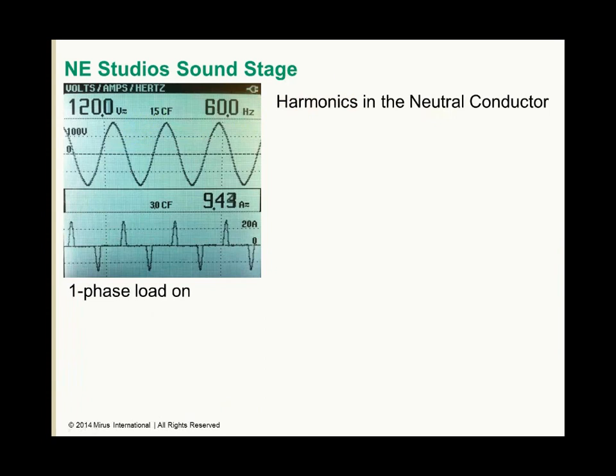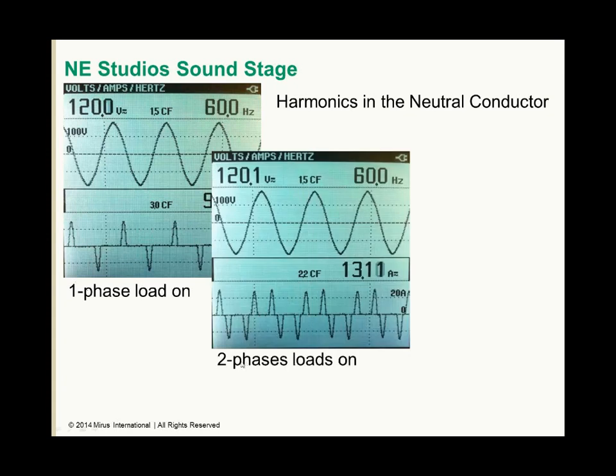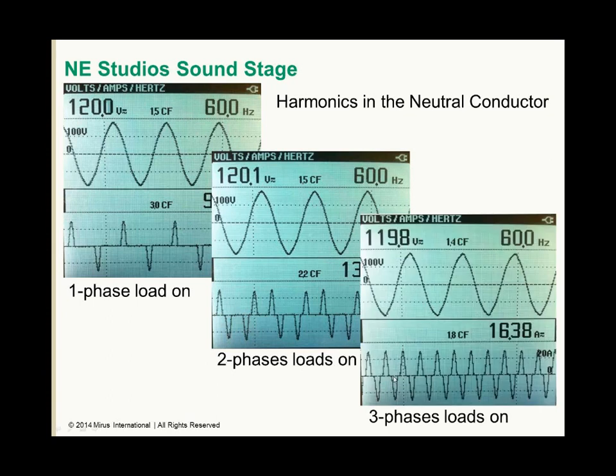Switching the loads while measuring the waveforms shows how the pulse phase currents add in the neutral to produce predominantly third harmonic current. So here we have the very sharp pulsed current being drawn by the nonlinear lighting. When we add a second load on the second phase, we can see the second pulse added there. When the third pulse gets added, we now have essentially third harmonic current on a 60 hertz system.